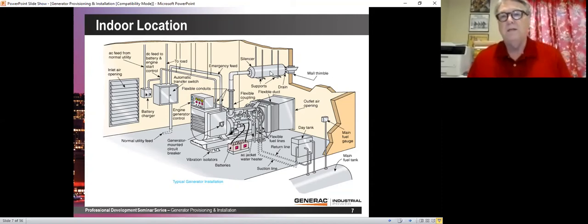Now, which way does this tilt? Does this tilt towards the generator, or does this tilt away from the generator and towards the outside? Well, to me, it pretty clearly tilts towards the generator. That's a code violation. This pipe must have a slight downward slope towards the outside, not towards the generator. The reason for that is when you combust materials, whether it be natural gas or diesel fuel, those are hydrocarbons, and hydrocarbons create water. And we do not want that water to flow back into the engine. It can ruin the engine.